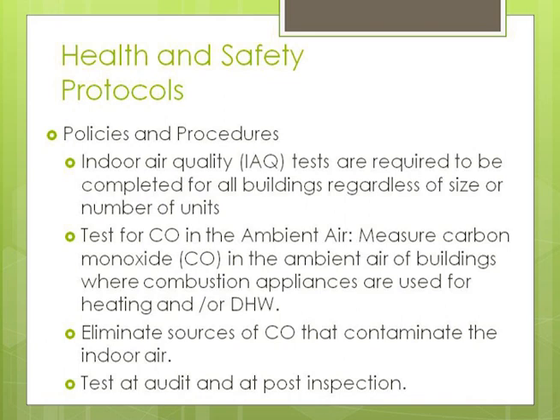We'd also go into what's called the CAZ — the Combustion Appliance Zone. You'll need to know that. The combustion appliance zone is the area where they have their furnace and their hot water heater. We'd have to test for carbon monoxide and also measure how much unburned fuel was in the exhaust to see if their furnace or hot water heater was operating efficiently.